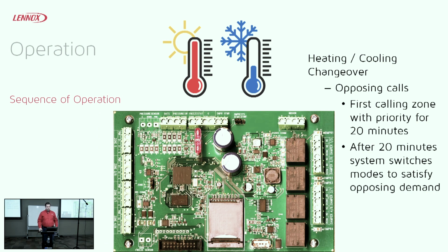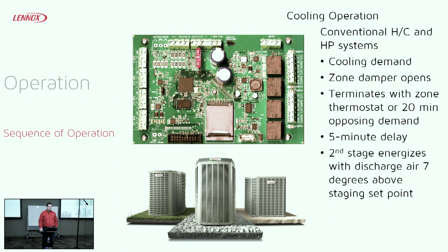The auto changeover, again, not something that y'all are going to deal with a whole lot, but essentially what it will do in one mode, it'll run for 20 minutes at a maximum trying to satisfy. If it needs to change over, it'll shut things down and run for 20 minutes in the opposite mode.